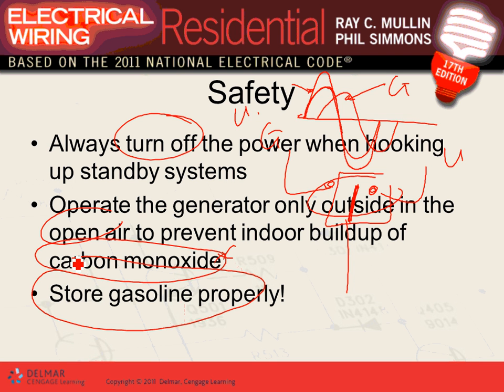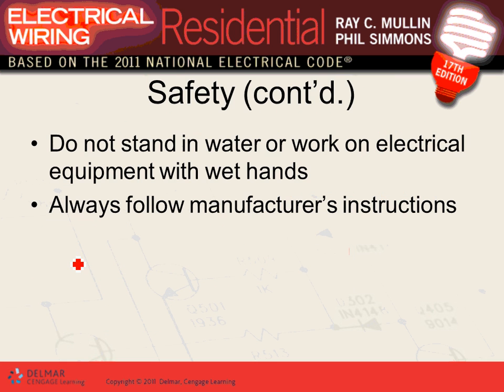Storage area. Store gasoline properly because these are flammable. So you get into storing the flammable material that you're going to burn, number one. Burning them, when you start them, you start them outside. So those are a few safety things that you have to do. When you're dealing with electrical, since your generator is outside now, you can't run it inside. We agreed on that. You have to store the flammable gasoline, diesel or natural gas. If you have a tank of natural gas or propane or whatever you're running your generator on, you're going to store it in a proper way, right?